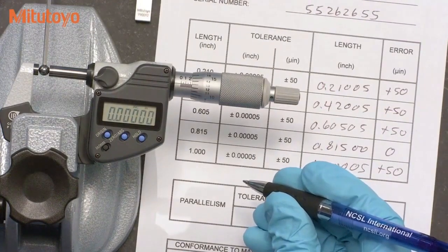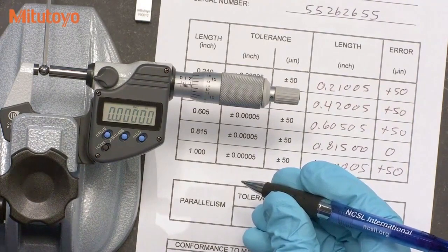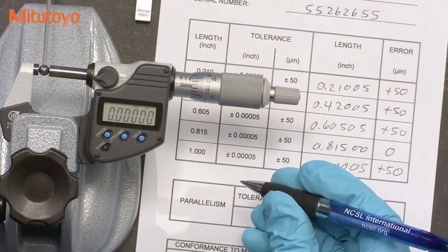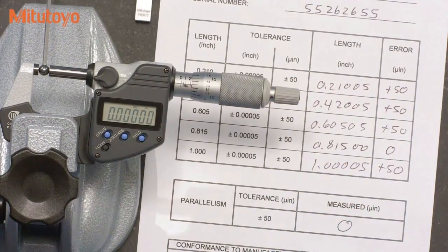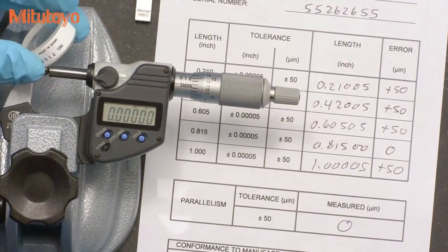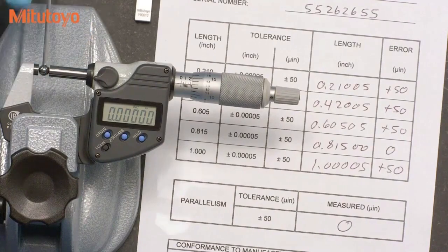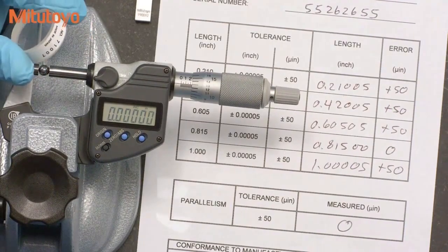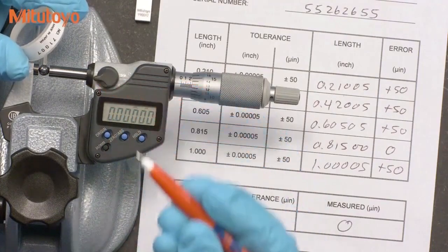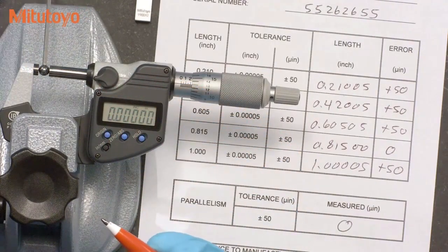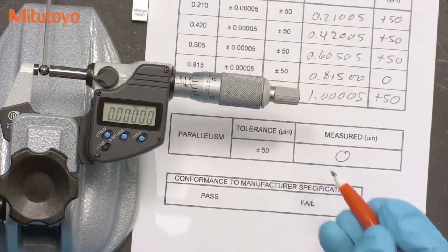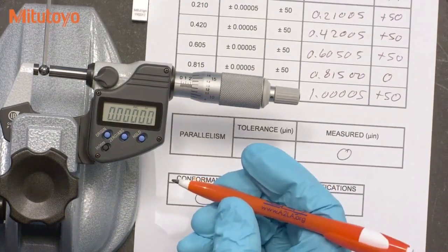Now, this method is generally not as accurate as using an optical parallel, but it's easy and efficient to do. When a calibration method is not easy to do and it is not the primary test, we often see labs skipping it. So we recommend using the ball because anybody can do it, and it's much better than not doing anything at all. We've also heard that some labs will use the optical parallel or optical flat if the test with the ball fails, because you can get a better idea of why it's failing. That seems like a pretty good idea, but we'll save using the optical parallel or flat for future episodes of the Metrology Training Lab. So that completes this micrometer calibration. It looks like this micrometer is in tolerance.